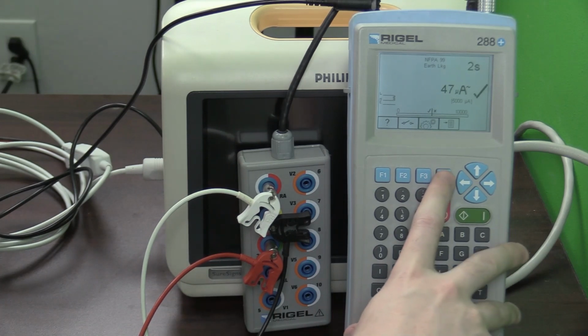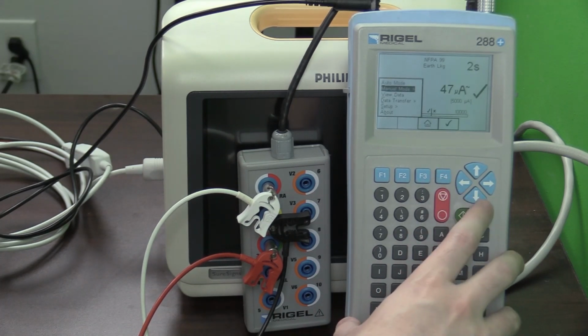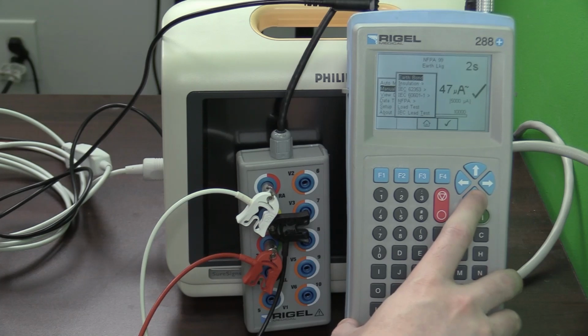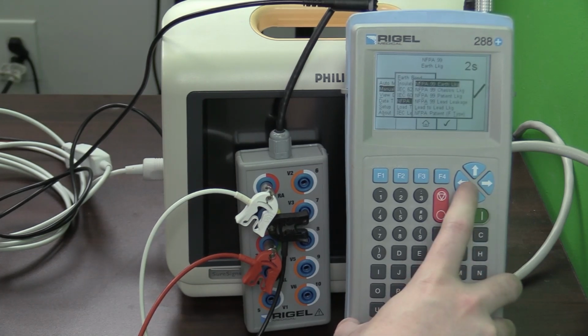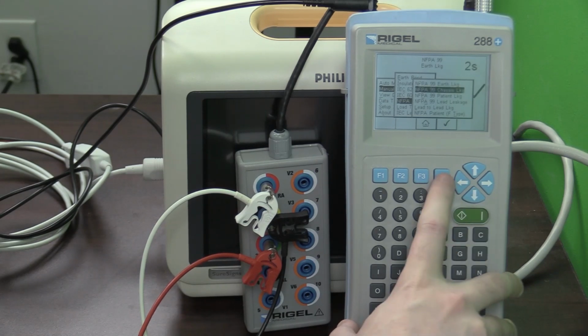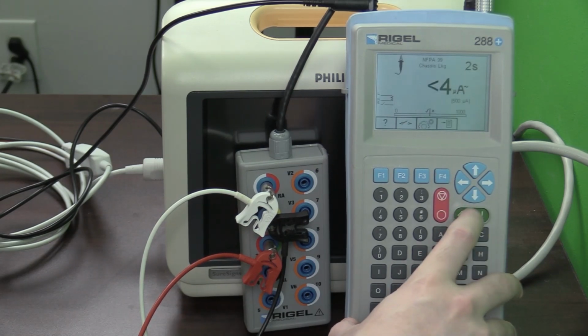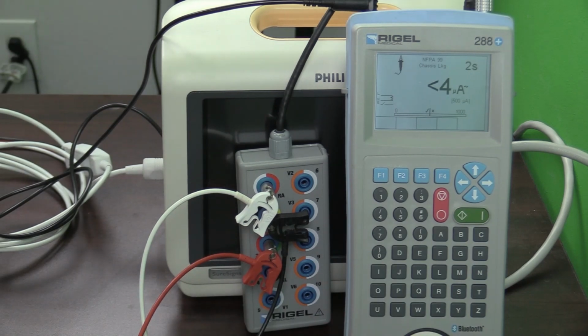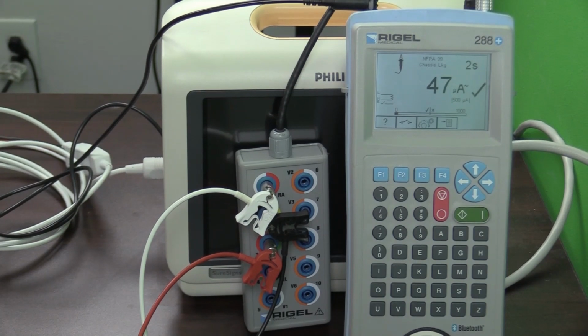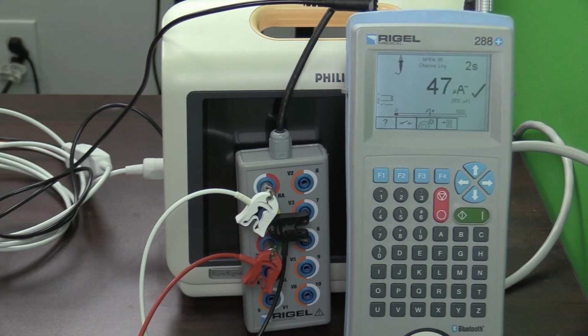Now we can hit F4 again to open up the menu, go down to manual, and select NFPA again. And now we are going to run the chassis leakage test. Select F4 to select the test, and the green button to start the test. And again, with this test, you'll need to record your values. This came in at 47 microamps, and the check mark will also display, meaning that the device has passed the test. Now we're going to start our next test.